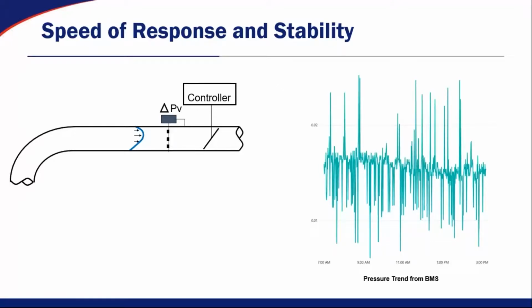So speed of response on these types of devices, again, will never be as fast as something that's using position-based control, because in this particular environment, you have to measure the velocity going through the ductwork. You have to record that velocity, do a calculation on where it falls in my flow curve, and then you have to readjust the damper position. So this is happening in real time. Velocity pressure changes, the controller takes a reading, the blade repositions the flow. Now I have a new pressure reading that goes back to the controller, and I have this cyclical motion where I'm reading, repositioning, reading, repositioning.